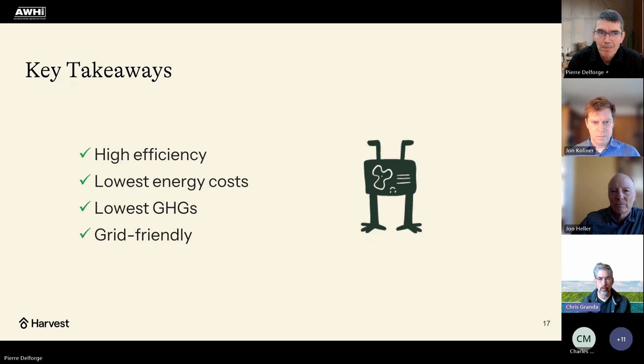Yeah, it's a good question. We do see a temperature drop — the efficiency drops at colder ambient for sure, and outdoor efficiency drops. The efficiency is also impacted by the type of emitter you have. In some cases, one of the Edmonton sites has a slant fin, which is an emitter that's not super great at doing single pass delivery or high temperature delta, so the efficiency of that particular system is a little lower. It's still good, but it's not in the 3 range. So we do see efficiency varying.